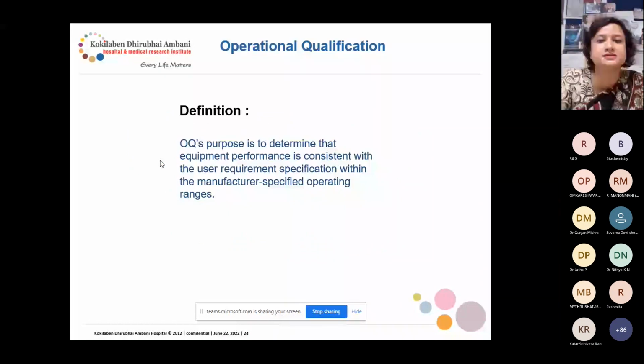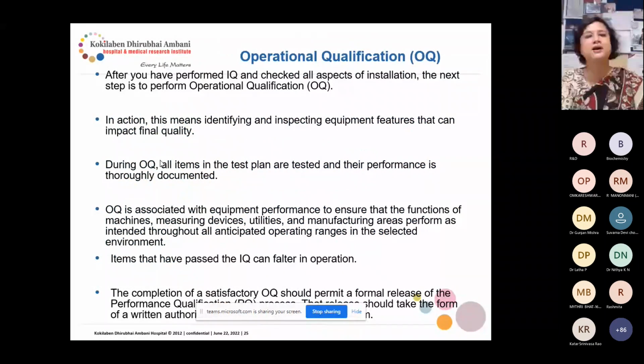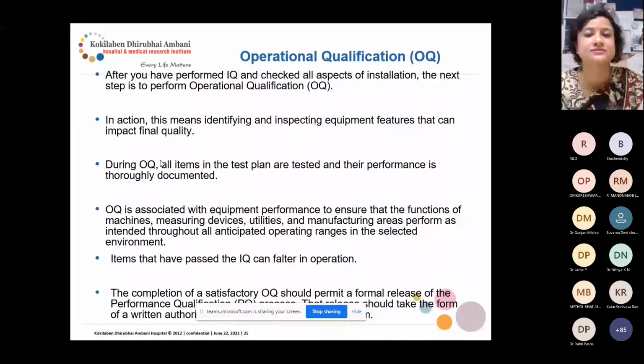Then operational qualification. Its purpose is to determine that the equipment performance is consistent with the user requirement specification within the manufacturer-specified operating ranges. If you have performed IQ and checked all aspects of installation, the next step is OQ. This means identifying and inspecting equipment features that can impact final quality. During OQ, all items in the test plans are tested and their performance is thoroughly documented. OQ is associated with equipment performance, to ensure that the functions of the machines, measuring devices, utilities, and manufacturing areas perform as intended throughout all anticipated operating ranges in the selected environments. Items that have passed the IQ can falter in operation. So the completion of a satisfactory OQ should permit a formal release of the performance qualification.